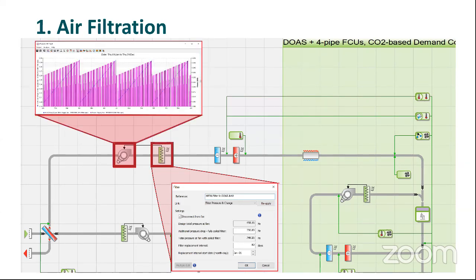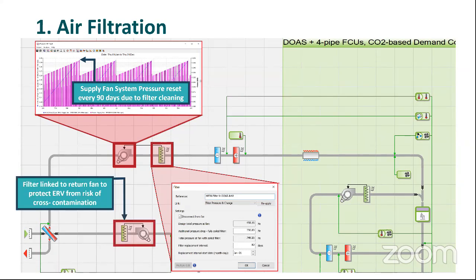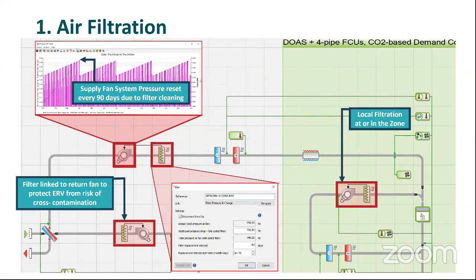This is basically the addition of HEPA filters or any type of filter to a typical HVAC system. In this case, the filter is to be cleaned every 90 days. You can see four spikes here showing system supply fan pressure resetting every 90 days once a soiled filter becomes a clean filter. Filtration systems can also be added to the return to protect energy recovery devices or localized at the zone level.